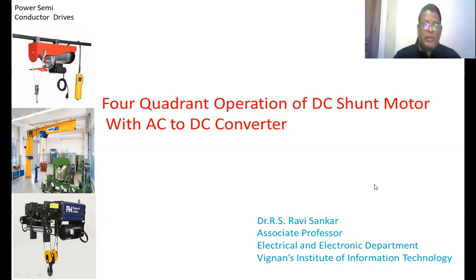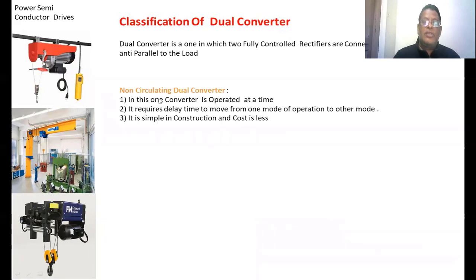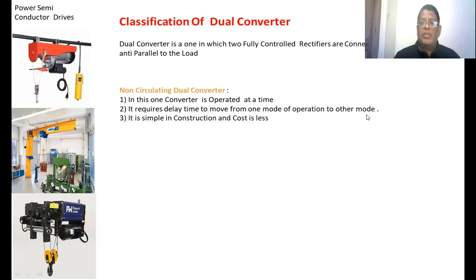We are going to see what a dual converter is and what types exist. A dual converter has two fully controlled rectifiers connected anti-parallel to the load. There are two types: the non-circulating dual converter, where only one converter operates at a time for any quadrant — forward motoring, braking, reverse motoring, or reverse braking. It requires a delay time to move from one mode to another, for example from forward motoring to reverse motoring. It is simple in construction and cost-effective.